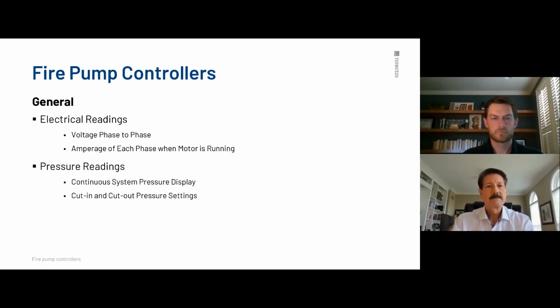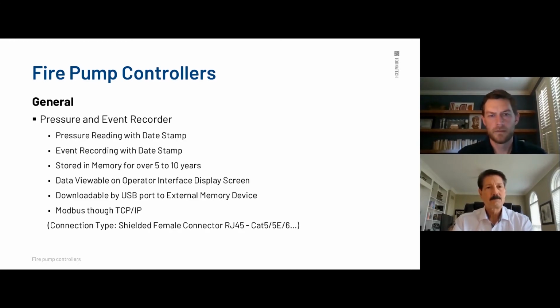Pressure readings, again, we need to know what the continuous system pressure is. We also need to show what the cut-in, cut-out is too. Pressure and event recorder. It's very critical for troubleshooting and determining if there's been any issues in the field as to what might have occurred. Again, by code, we need to have a pressure reading with a date stamp stored in the memory for up to 5 to 10 years.